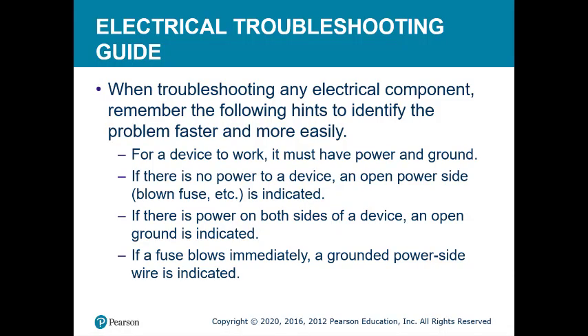So as we summarize electrical troubleshooting, remember for a device to work, it must have power and ground. If there is no power to a device, an open on the power side, like a blown fuse, is indicated. If there is power on both sides of a device, then it's probably an open on the ground side. If a fuse blows immediately, it's most likely a short circuit, which would indicate a grounded power side wire.